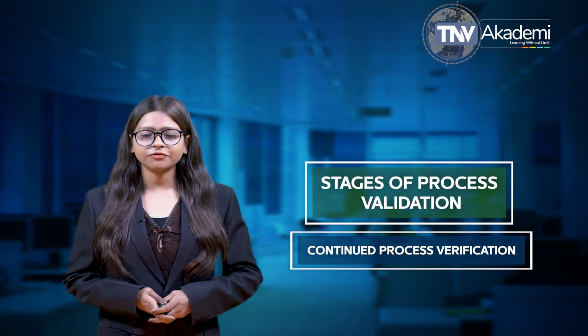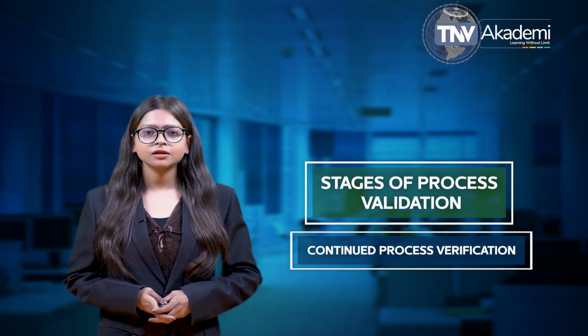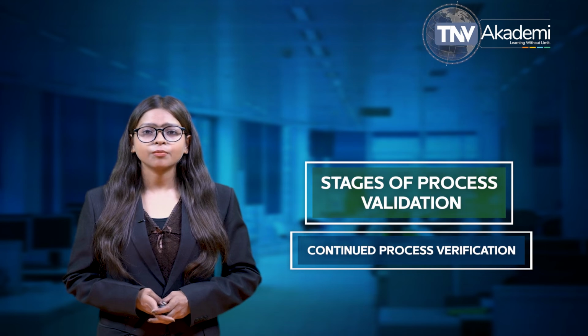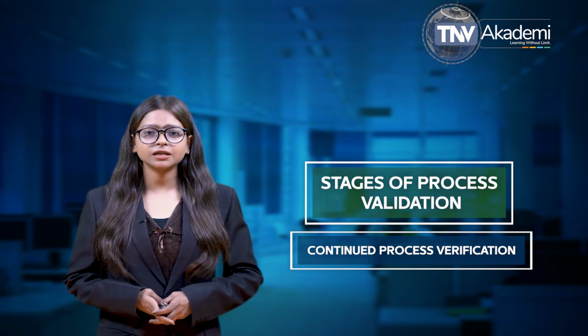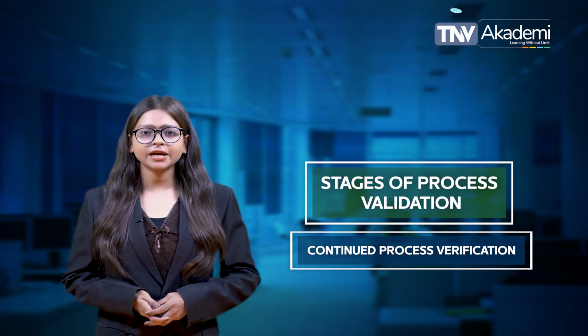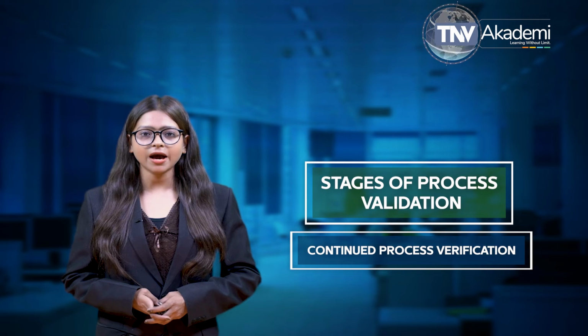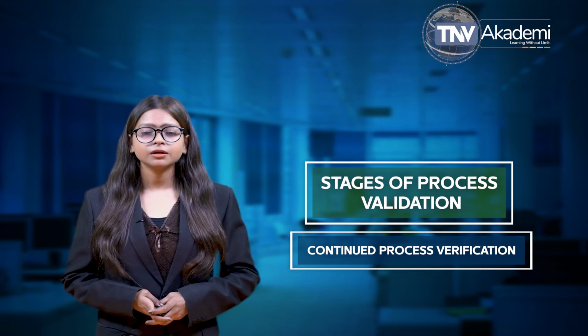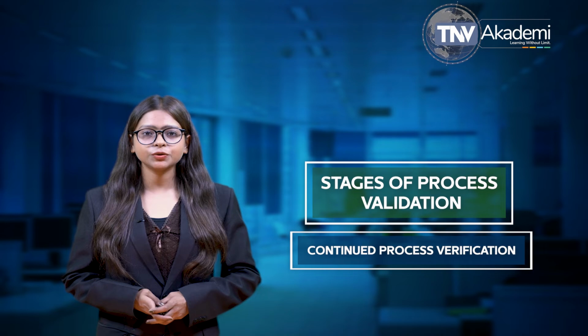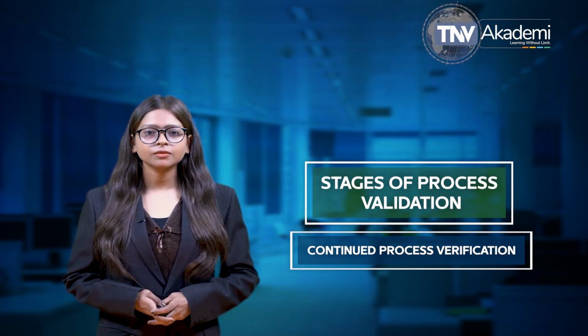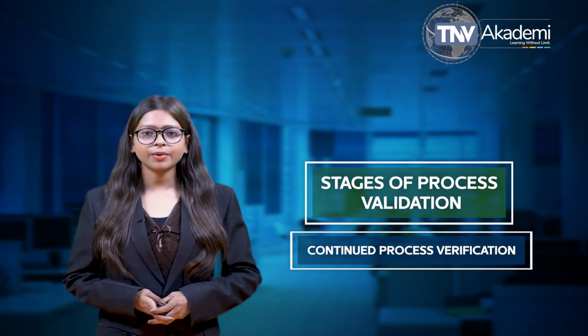Continued process verification often incorporates the use of statistical process control (SPC), the continuous monitoring and sampling of process parameters and quality attributes, and the scheduled maintenance of the facility, utilities and equipment. It is essential for good documentation practices to be employed throughout the validation process.